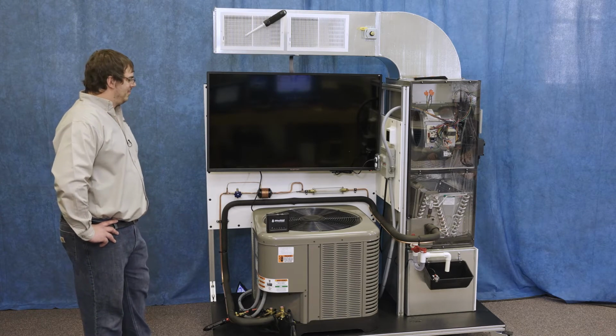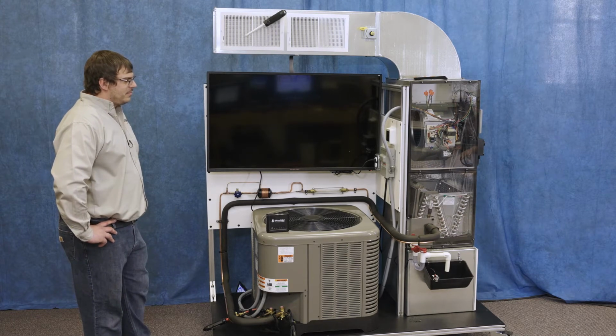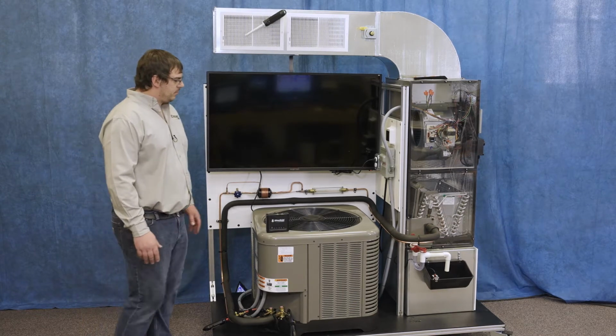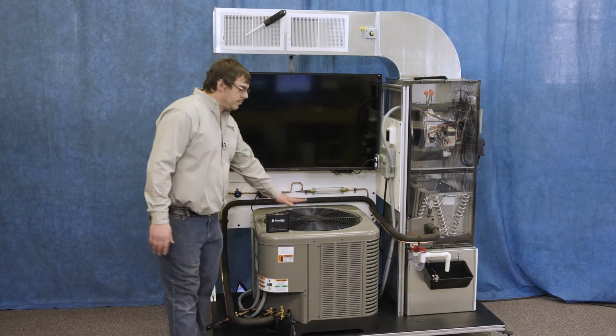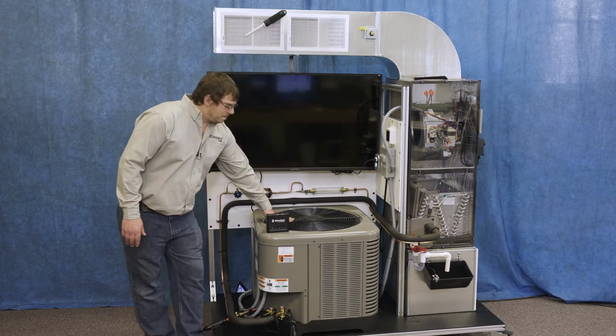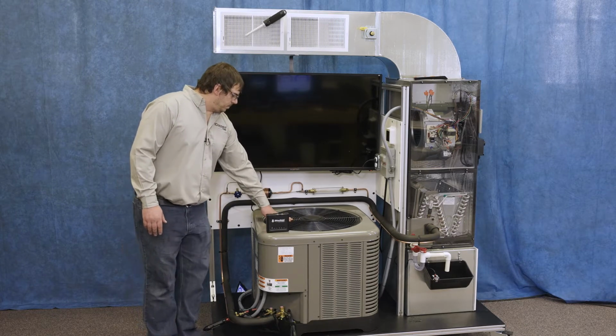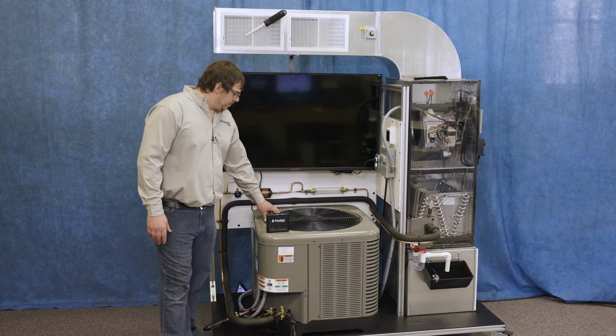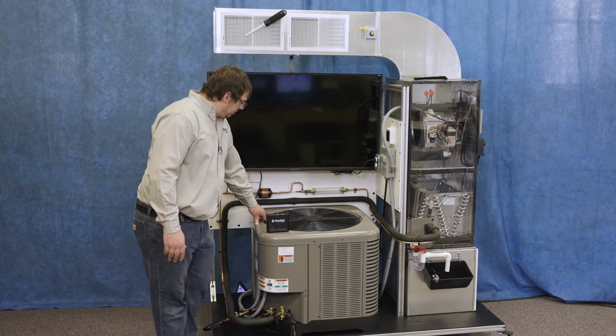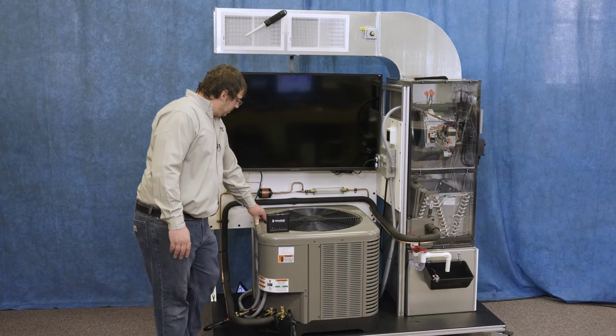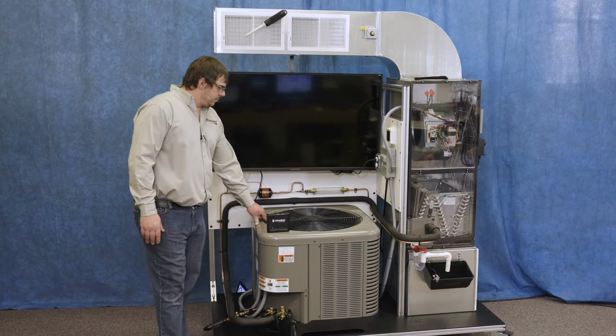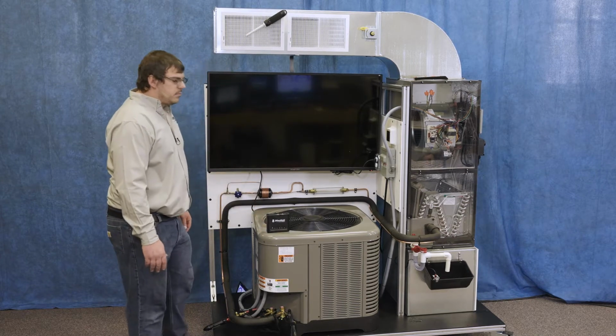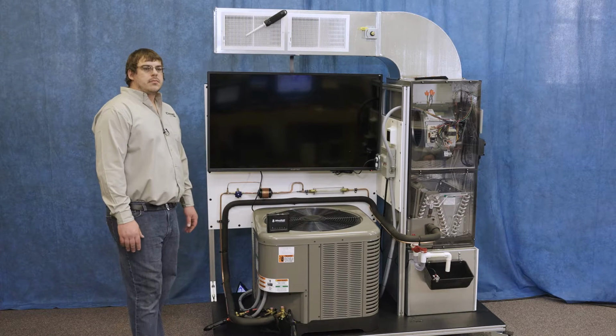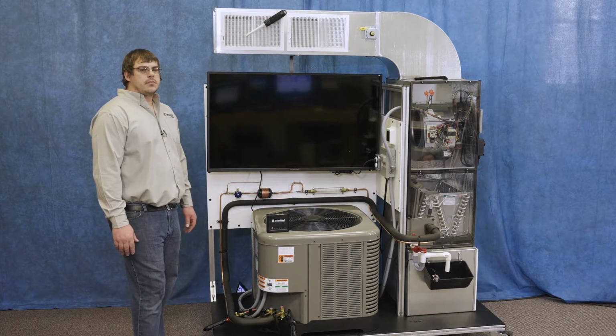All right, so Nick, let's go over here and look. We've got a split system here. First off, Nick, go ahead and put your hand there on the outdoor unit. Now, this outdoor unit has inside of it the condenser coil as well as the compressor and all the controls that are associated with it. On the board, we may just have the 4 major components broken out into 4 sections, but here it's all inside this outdoor unit. So there's the outdoor unit.